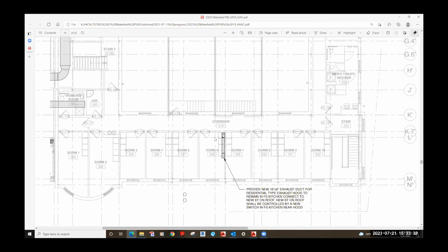What I'm thinking is, originally every time we've looked at this, we were alerted to the concern of when they're cooking something on the fire station side, it's getting over to the police side. So our original intent was always that maybe there was a deficiency with this duct, and that's why we were calling for it to be replaced. What could be happening is because that gooseneck is coming out on the roof, maybe it's being pulled in through the RTU near the gooseneck, the outdoor air intake.